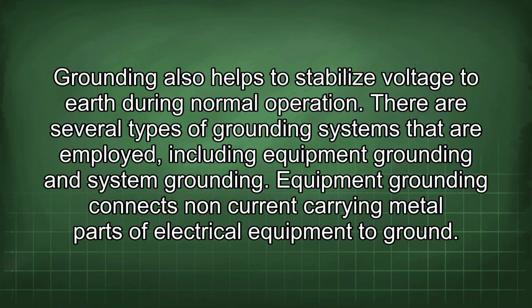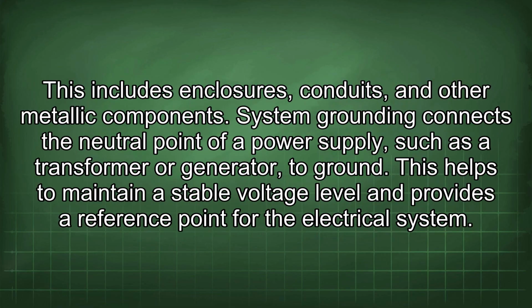There are several types of grounding systems that are employed, including equipment grounding and system grounding. Equipment grounding connects non-current carrying metal parts of electrical equipment to ground. This includes enclosures, conduits, and other metallic components. System grounding connects the neutral point of a power supply, such as a transformer or generator, to ground. This helps to maintain a stable voltage level and provides a reference point for the electrical system.